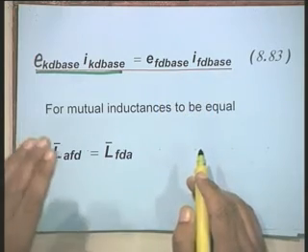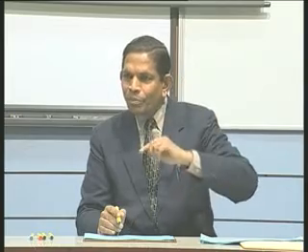It means now we can conclude actually that these 3 windings, one the field winding, another the stator winding, third the direct axis amortisseur winding. Now, if you want to make these mutual inductances reciprocal, then the volt ampere base in the stator circuit must be equal to the volt ampere base in the field circuit and the volt ampere base in the amortisseur circuit, because in the stator the volt ampere base is equal to the 3-phase VA base, the total MVA rating.